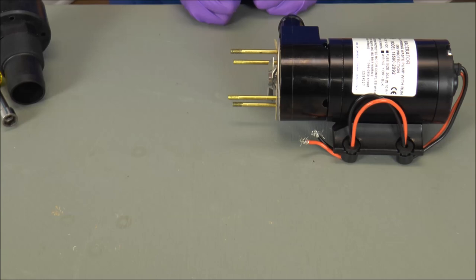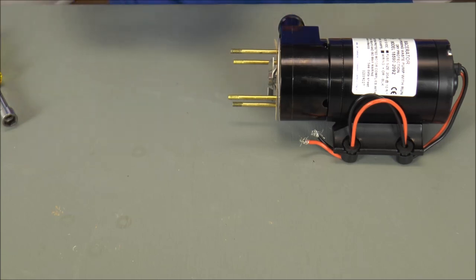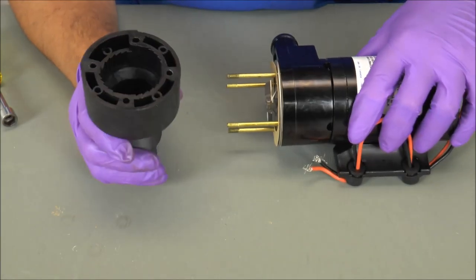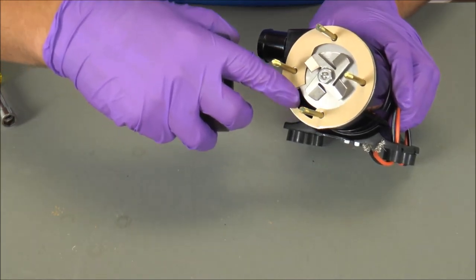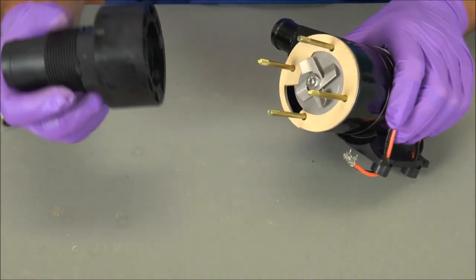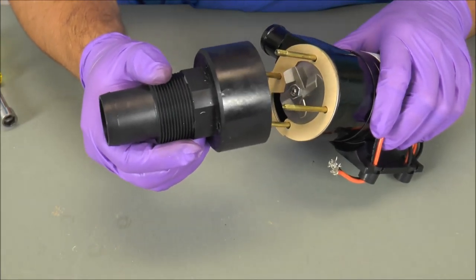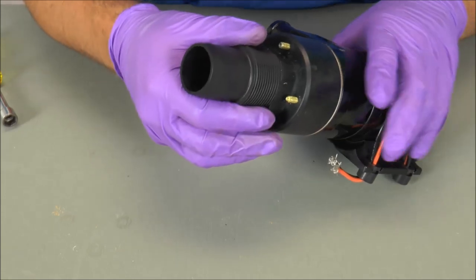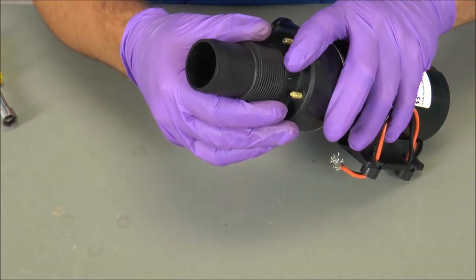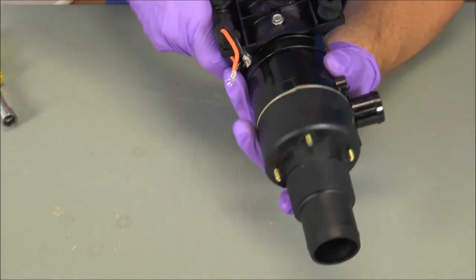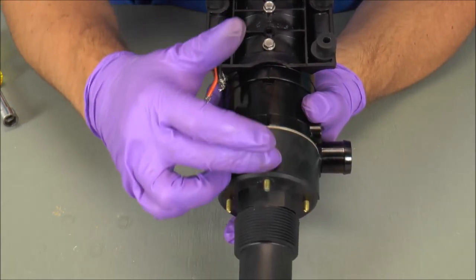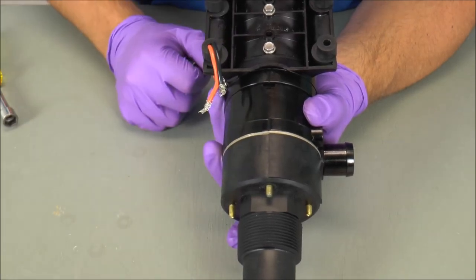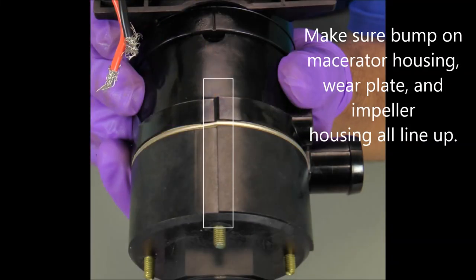So now we're going to reassemble the macerator housing. All you simply do is slide it on, however, you want to make sure that the cut out in the macerator housing lines up with the open portion of the macerator. So again, we simply slide on the macerator housing, making sure the cut out matches. Now if you're unsure, one way to confirm this is flipping it upside down, and you'll see that there's a little bump on both the macerator housing and the macerator. These two will line up.